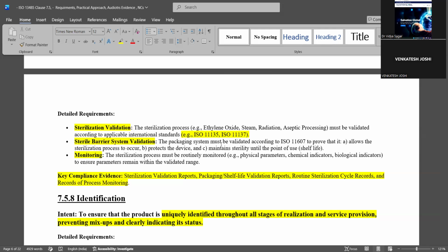The second is monitoring by chemical indicators, but they are not reliable. In some cases of sterilization, like steam sterilization, you can depend on chemical indicators. Ethylene oxide, you can depend. But in some, like gamma sterilization and aseptic sterilization, you can't depend on indicators. Basically, you don't use chemical indicators; we use biological indicators, which are more reliable. So first is sterilization validation, second is the sterile barrier system, and the third is monitoring of sterilization by different parameters like sterility testing, bioburden, endotoxin, chemical indicators, and biological indicators.